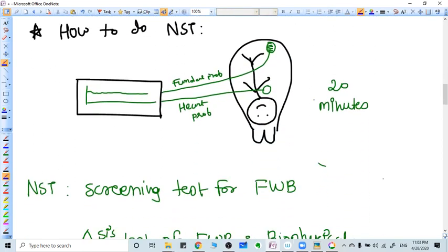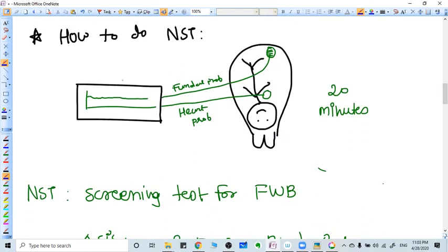Now, how we do the NST? The CTG machine has two probes. The one probe is fundal probe that measures the uterine contraction. The second probe is fetal heart probe which measures the fetal heart.